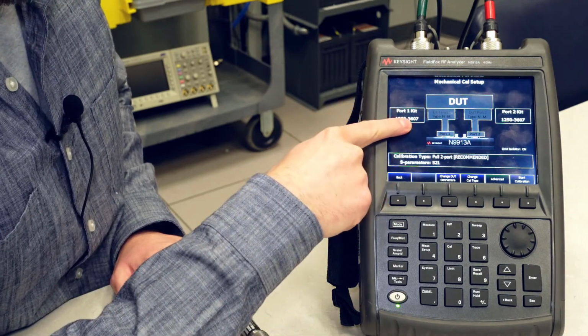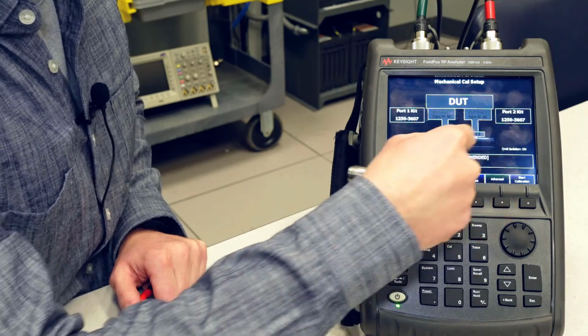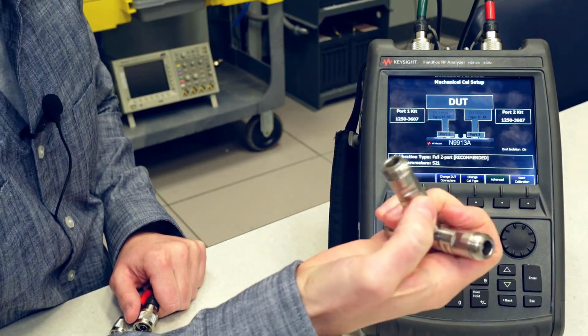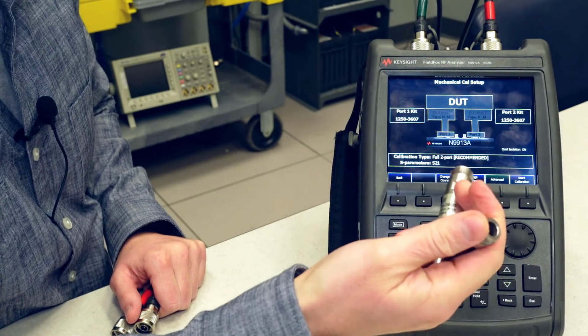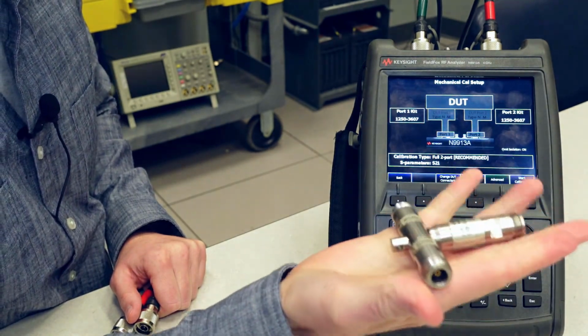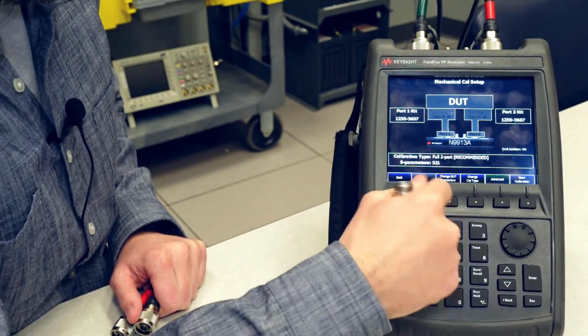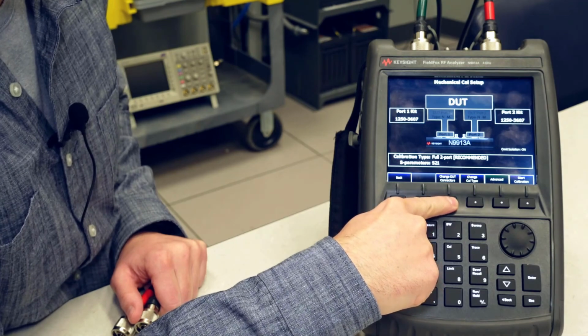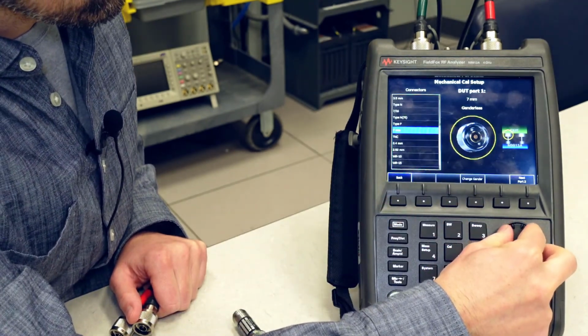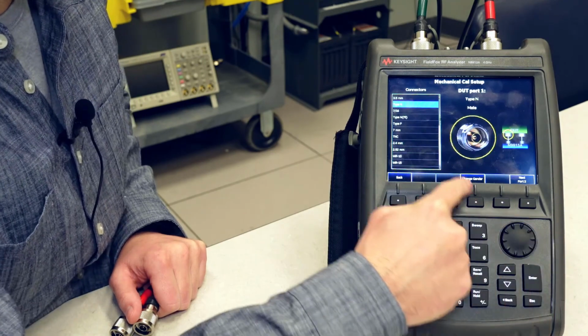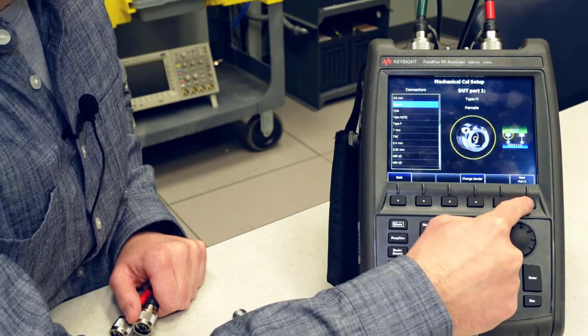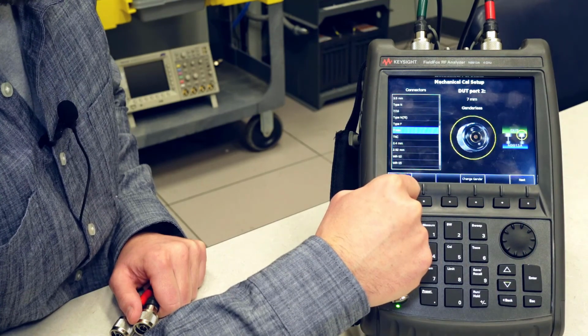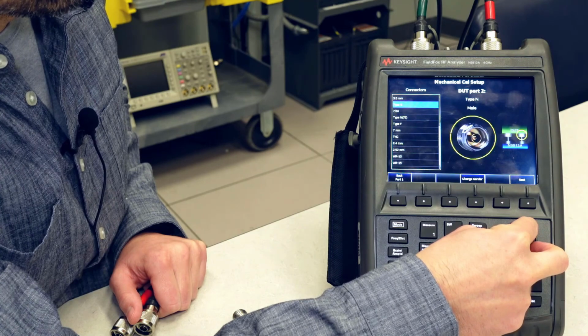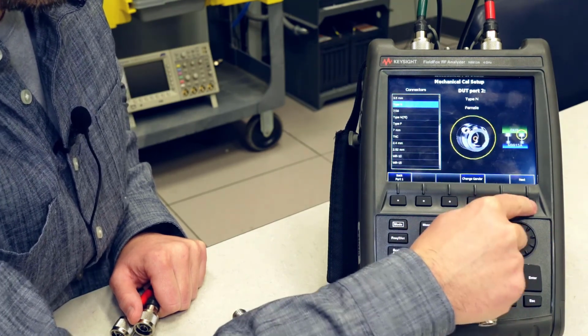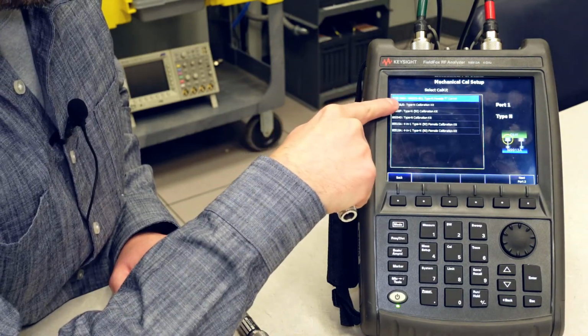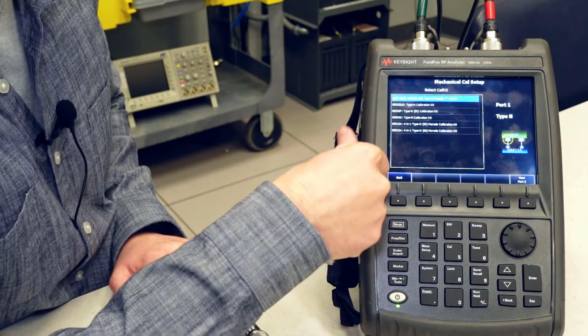And you can see that it selected the 3607 calibration kit. And that's this, but with male N-type connectors on all the sides. So we can actually change this to match the calibration T that I have by selecting Change DUT Connectors. And then using the scroll wheel, you can select type N and then change gender. And then do that for the next port, port 2, and then next. And now it's bringing up all the calibration kits that would match that connection type.